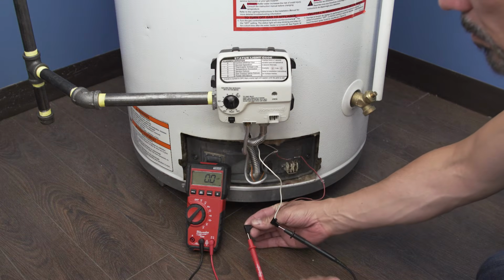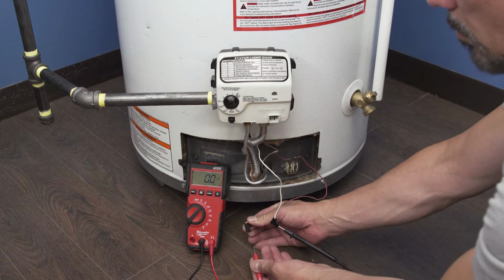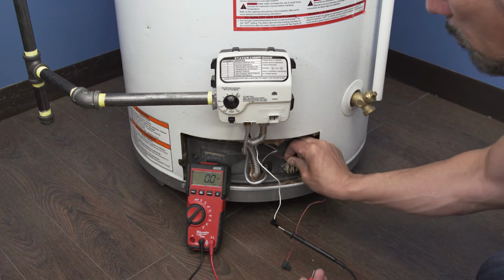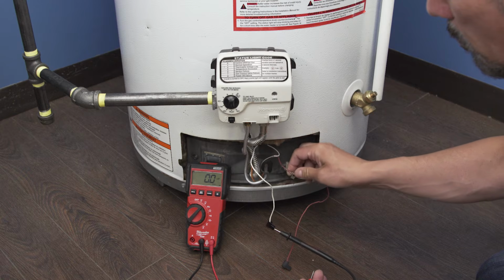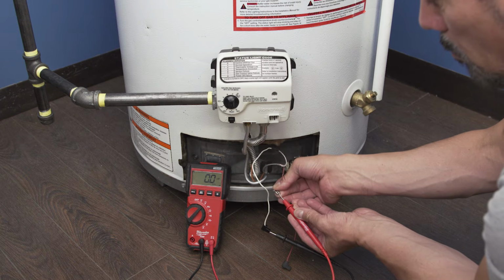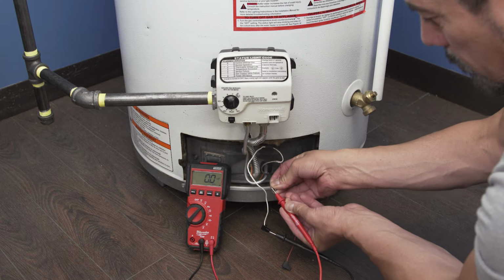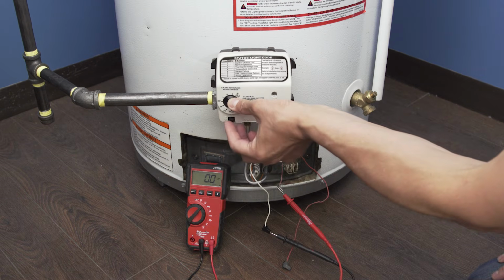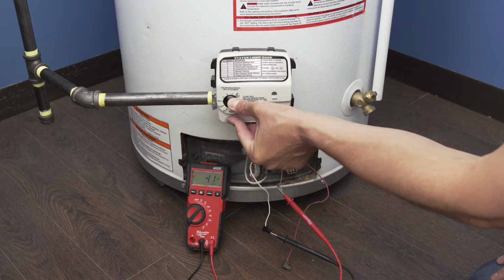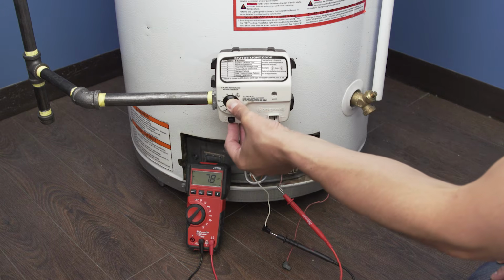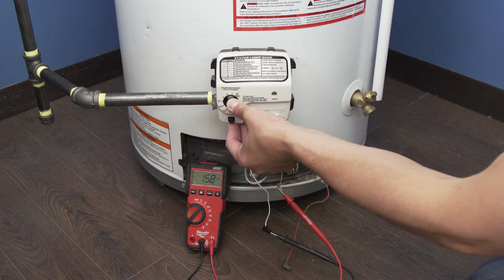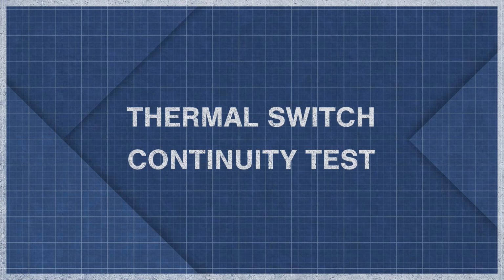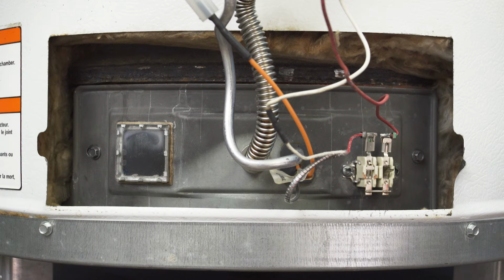If there is no voltage during the first test, then isolate the thermopile. Remove the wire leading to the thermal switch. Now connect the multimeter probe to the thermopile wire. Relight the pilot and measure the voltage. If the voltage is low or if there is no voltage, then replace the thermopile. If the thermopile is healthy, then it's possible that the thermal cutoff switch is faulty.